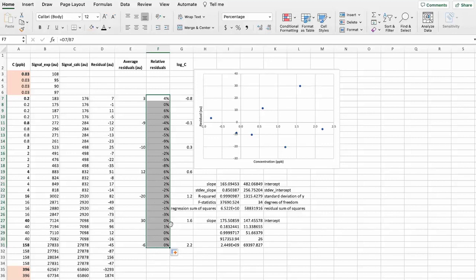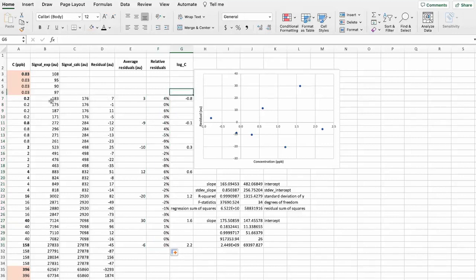But they are all absolute value is below 20%. So which means that also based on the Sante guidelines, we can actually say that this calibration is linear in the range from 0.2 to 158.